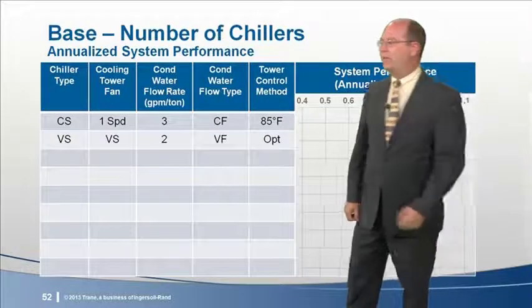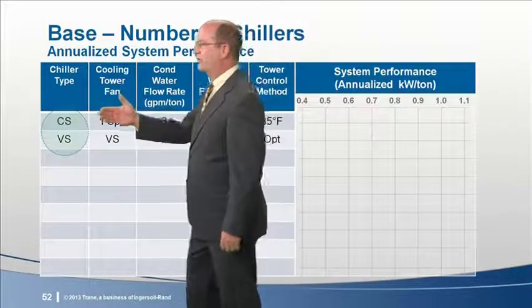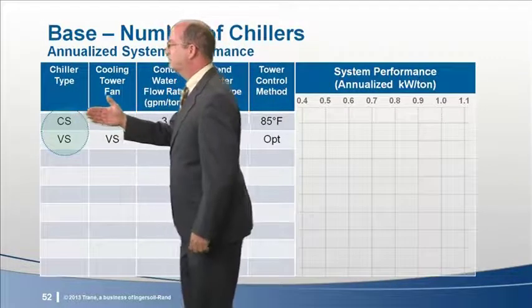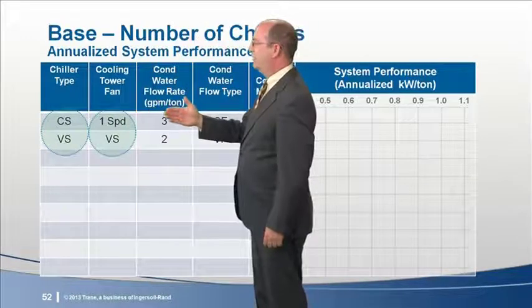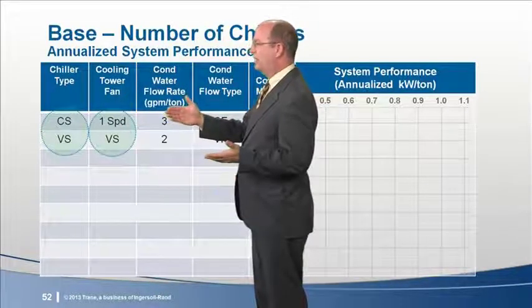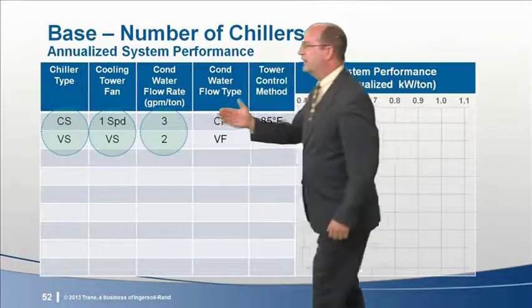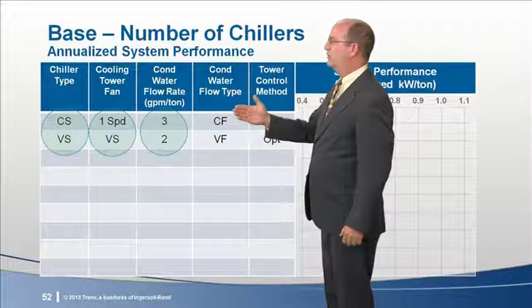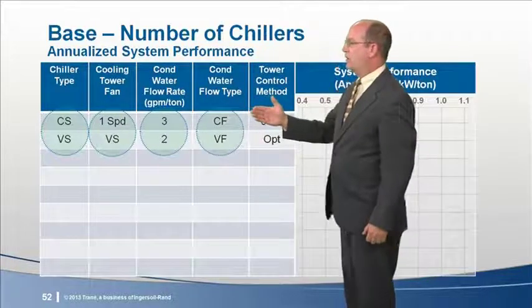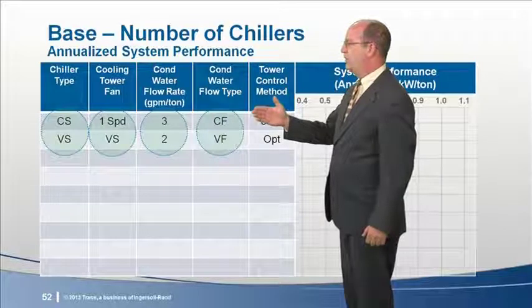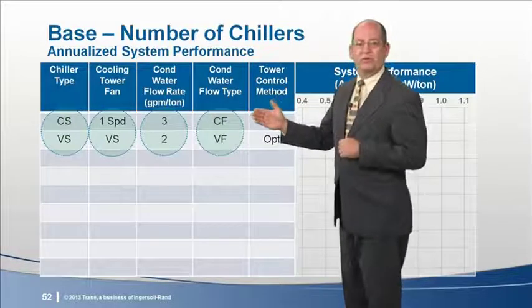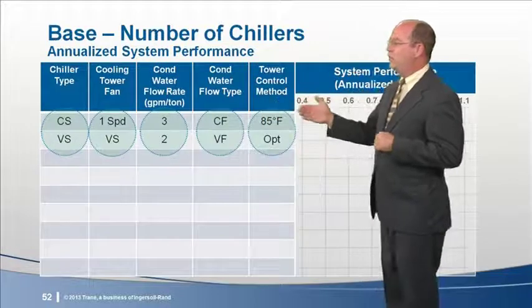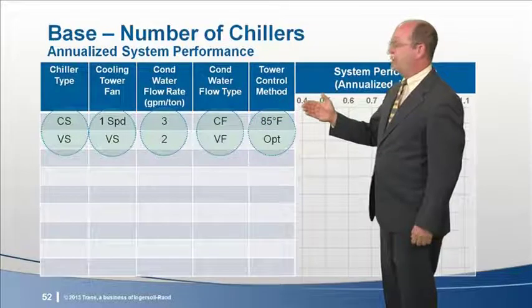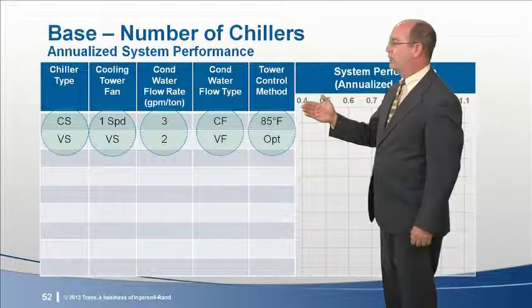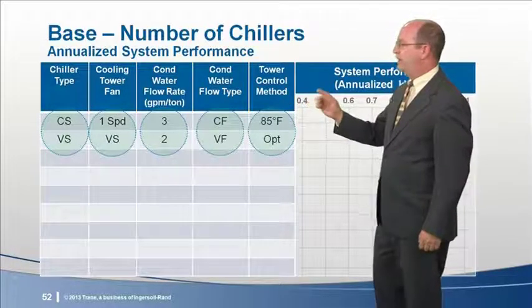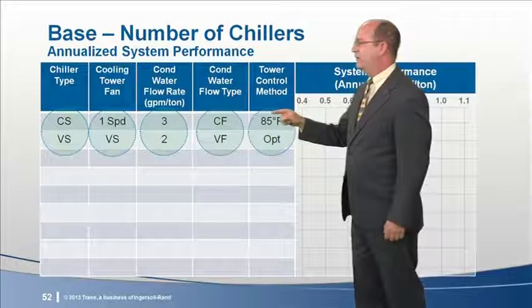For each alternative, we'll have the following monikers on the chart. For chiller type, constant speed or variable speed. Cooling tower fans, either single speed or variable speed. When a chiller is added, so is a cooling tower fan. Condenser water pump design flow rate in units of GPM per ton. The condenser water pump, either constant flow or variable flow, and when a chiller is added, so is the condenser water pump. Finally, there are many cooling tower control methods. Today we'll compare fixed set point control and optimized control. We designate the fixed set point control by showing that set point, for example, 85 degrees, in the table.